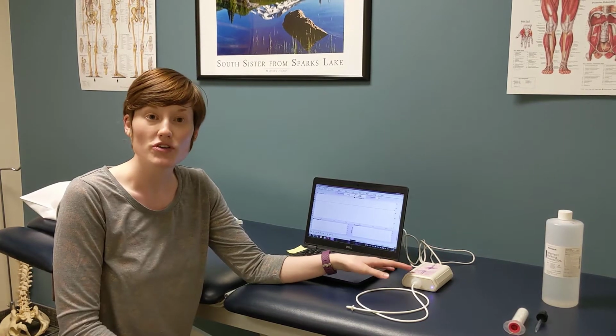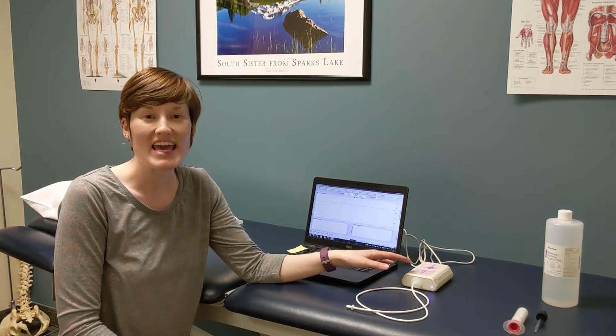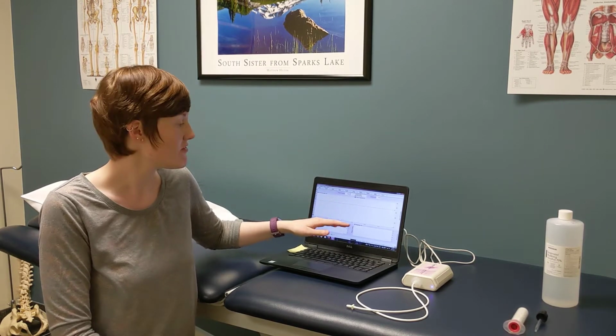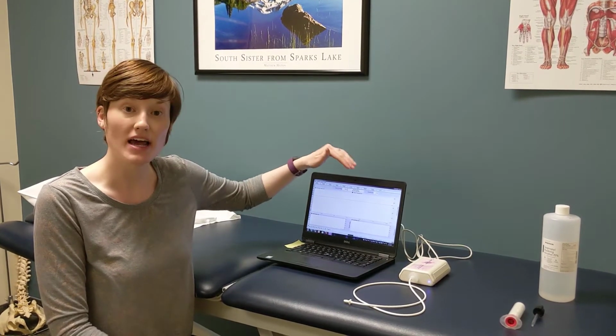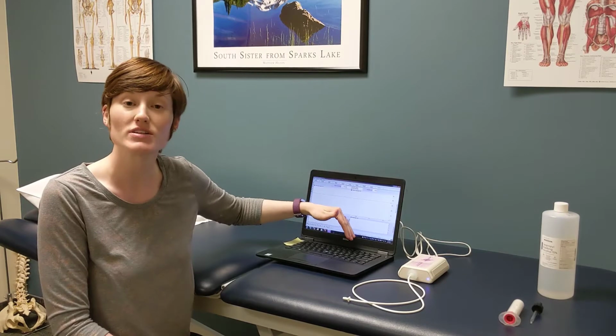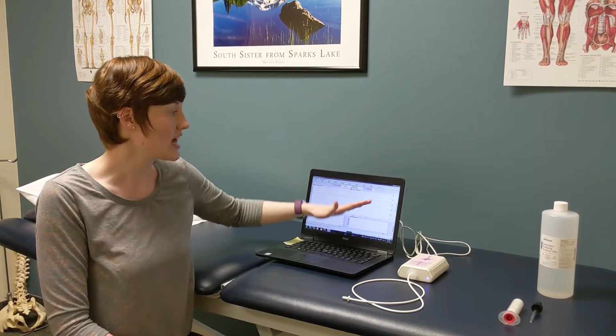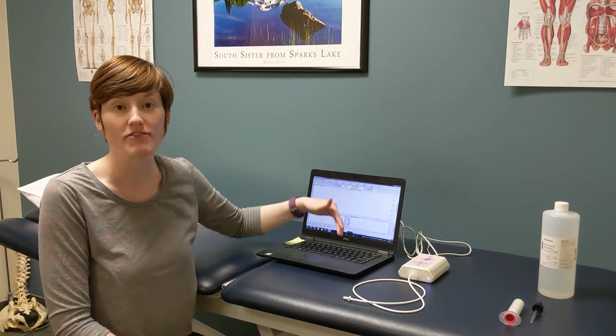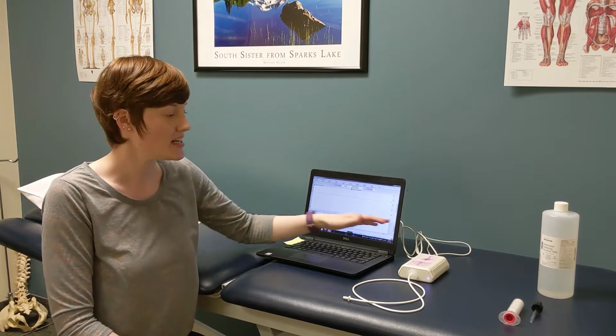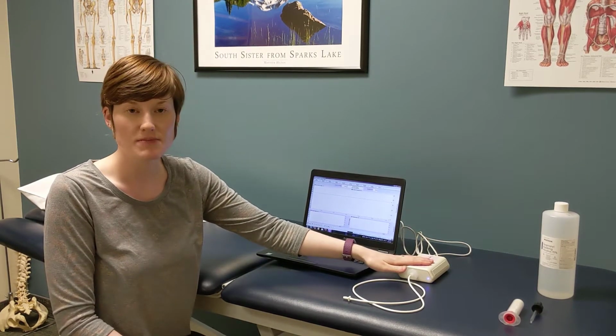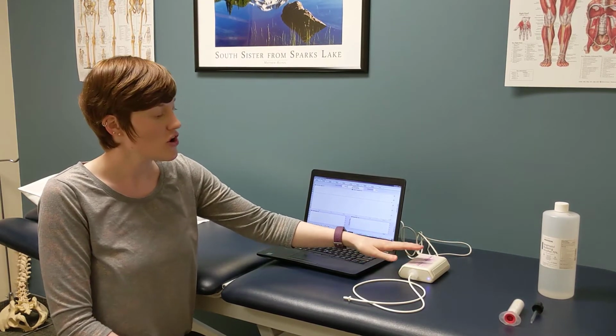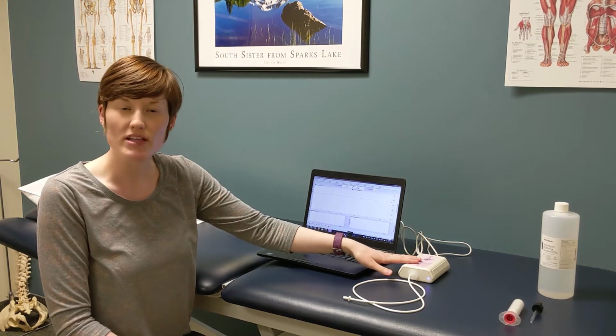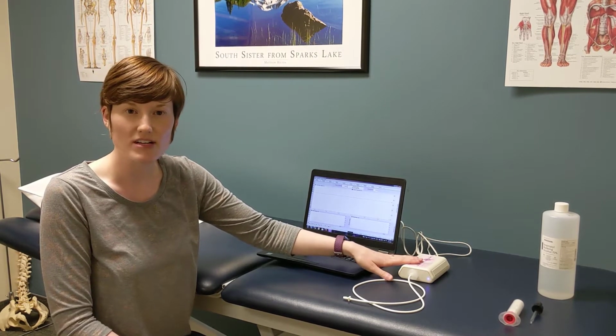So you'll know you'll need to calibrate the CapnoTrainer if you're getting very inconsistent readings, or if the baseline, when the carbon dioxide goes back down, does not go to zero. It's going to be a little higher, or perhaps it's even jumping off the screen. That lets you know that there may be some water in the system and you'll need to get it out. You'll also want to just do it fairly regularly just to maintain the integrity of the device.